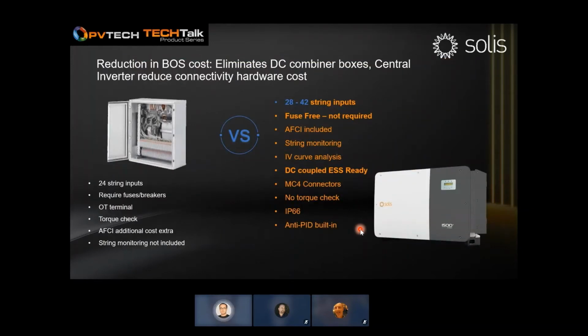Now, let's talk about how this inverter will completely replace a DC combiner box, which usually is the challenge of other smaller size string inverters. Looking at the DC combiner box, it usually has 24 string inputs, requires fuse or breaker, uses OT terminals that require regular torque checks. AFCI is always additional to the existing cost, and string monitoring is not included. So we don't want to use it.